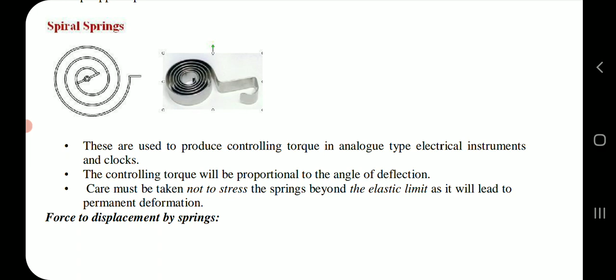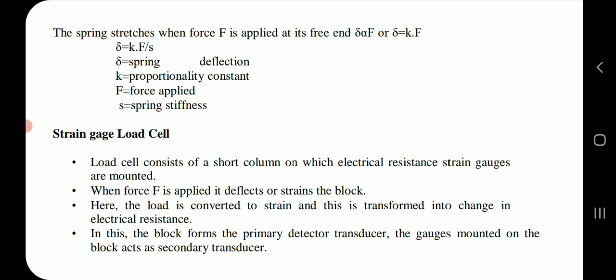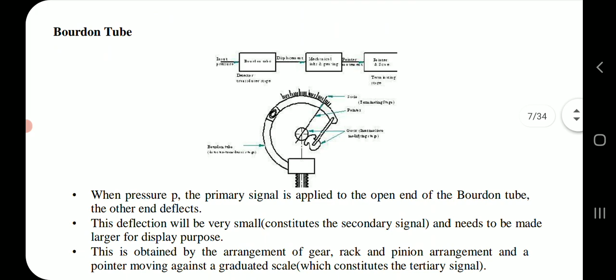Strain gauge load cell. A load cell consists of a short column on which electrical resistance strain gauges are mounted. When force is applied, it deflects or strains the block. Here, the load is converted to strain and this is transformed into change in electrical resistance. In this, the block forms the primary detector transducer. The gauges mounted on the block act as secondary transducer.